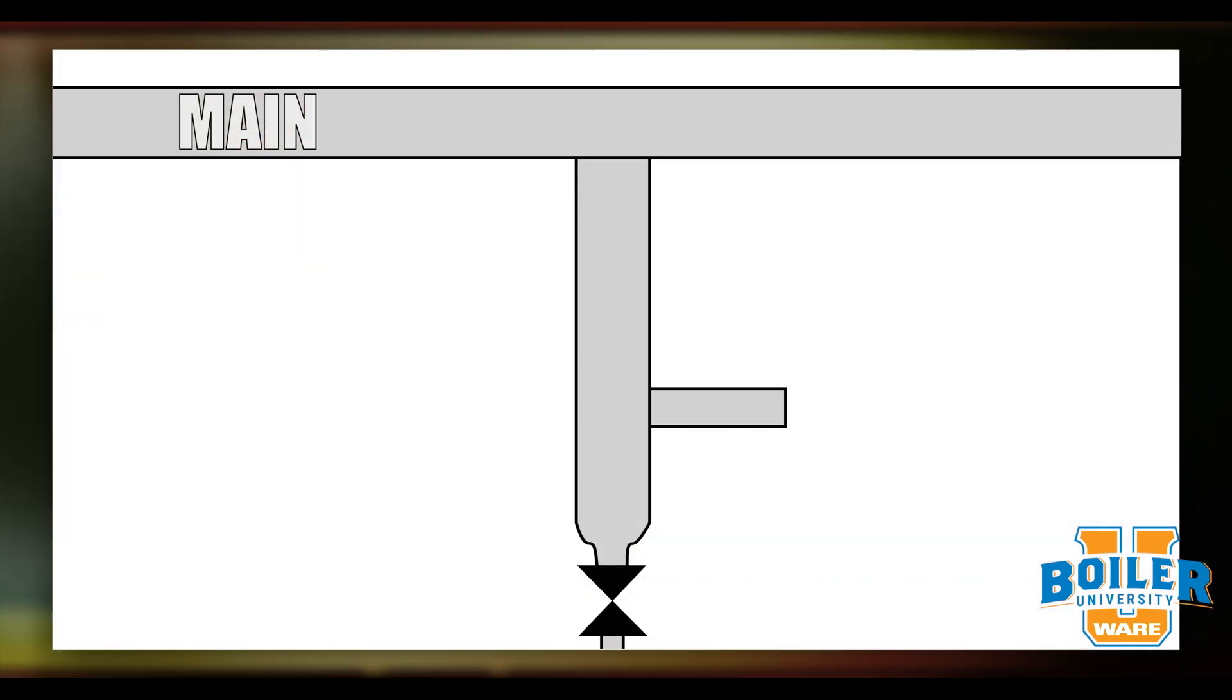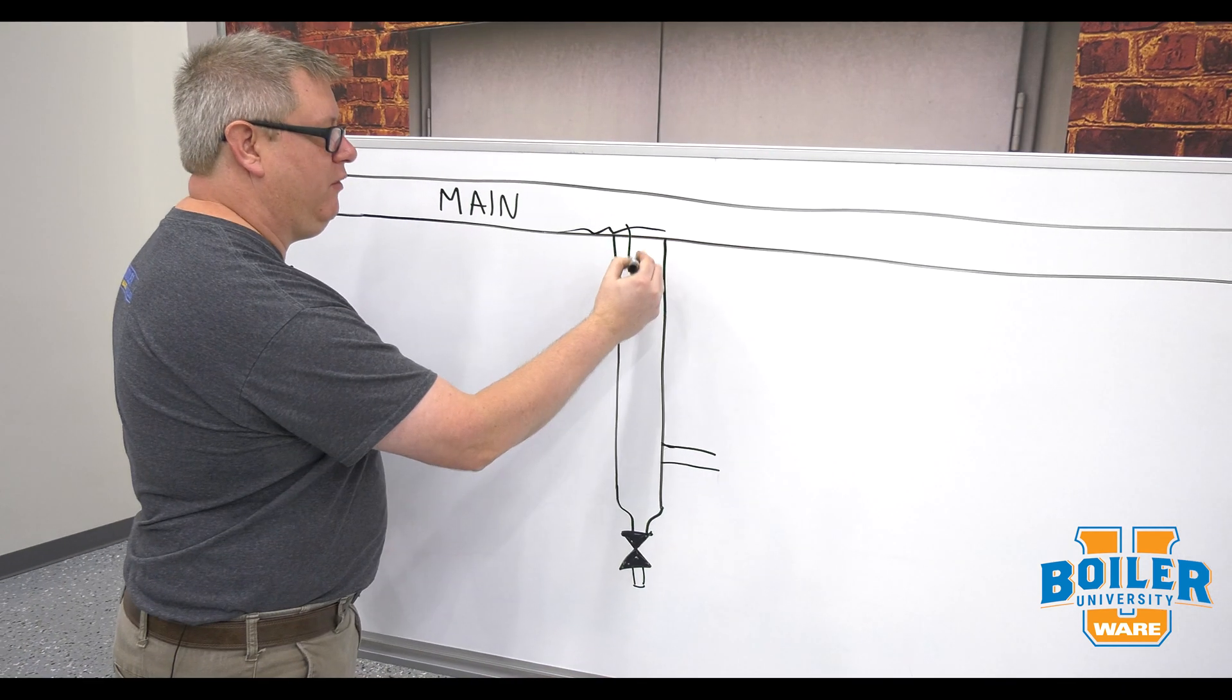So here we've got a main steam line, let's say it's three inch, so we're going to go ahead and use a full line size drip leg and that's so that our condensate can't just skip over, it's going to fall down in there.